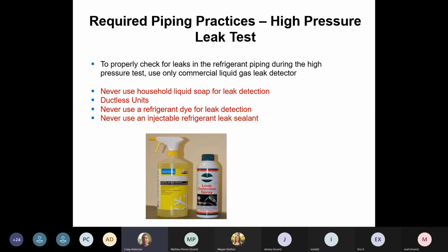Standard air conditioners, they have no problem recommending leak dye, refrigerant, or sealant in their systems. The only time you do not want to use that in a system is when you start getting into variable speed air conditioners or mini splits. They do not recommend any leak detection or leak sealant in those systems.